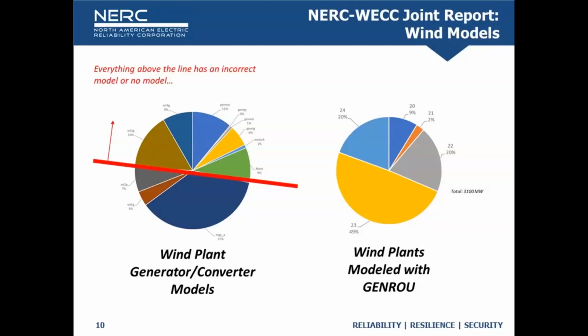Let's go a little deeper. About 3,100 megawatts are representing wind turbines with GENROU models. We thought maybe those are legacy - old type ones and twos - and maybe we could give them an out, saying they did the best they could given the technology available at the time. But we found half the fleet are type 3 wind turbines, fairly new ones, modeled with GENROU models. About 20% are type 4, and the remaining 30% are type 1s and 2s. Actually, for 10% of that, the transmission planner said they didn't have a clue what type of turbines were out there and couldn't get that information from the generator owner. That's concerning in and of itself.